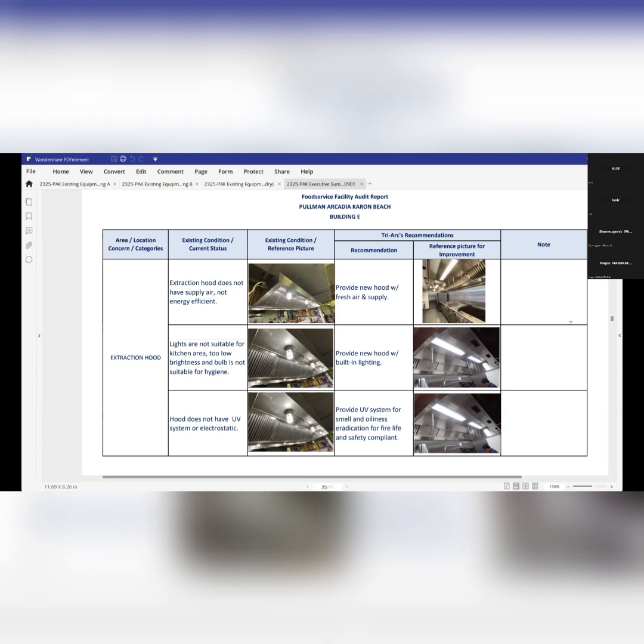The light bulbs also aren't bright enough, and they're not vapor-proof rated. Also, the new hood would have UV or electrostatic filters. This is what we'd recommend in the new design - what you see on the right side is the improvement. So this is one example, the exhaust hood.